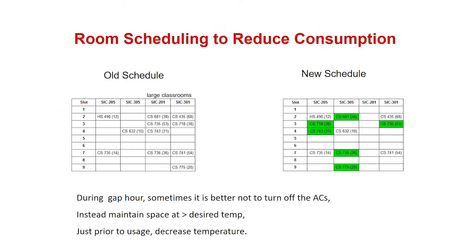And now, we also go one more step and look at the schedule that we have for the classrooms. And we can convert this schedule into a newer schedule, which is going to take into account the pre-cooling that happens when you have a meeting in the room. And you want to capitalize on the pre-cooling and use the space that's already cold or properly climate controlled for holding another meeting or another class. Secondly, we want to also have room sizes chosen according to the occupancy required for the particular meeting.